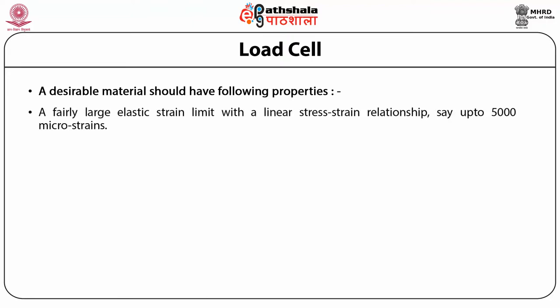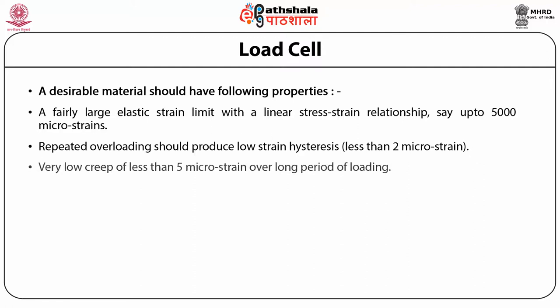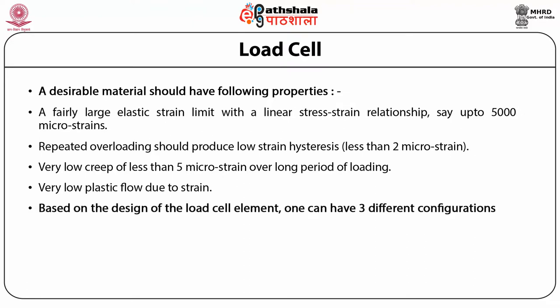One, a fairly large elastic strain limit with a linear stress-strain relationship, say up to 5000 microstrains. Second, repeated overloading should produce low strain hysteresis, i.e. less than 2 microstrain. Third, very low creep of less than 5 microstrain over long period of loading. And finally, very low plastic flow due to strain.